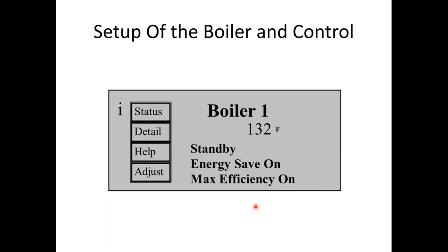So, setting up the boiler and the control. When you first turn this product on, this is the screen you're going to be greeted with. It's going to have your status, detail, help, and adjust. It'll say boiler; if you're using a combi, it'll say boiler/combi. This right here will give you your call for heat or what the boiler is doing. Currently, there's no call for heat. It's in standby. If it was responding to a call for heat, it would say central heat or domestic hot water.